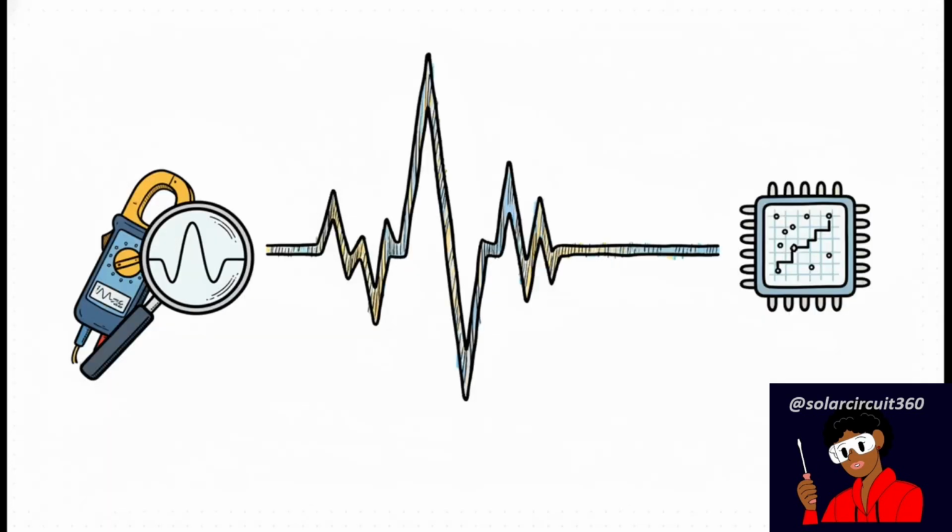This brilliantly illustrates the core conflict. Out in the real world, you've got your handheld clamp meter measuring true RMS current safely on the outside. But inside, you've got the internal logic of the inverter's firmware relying on a completely different internal sampling method. That is exactly why your trusty clamp meter might show a perfectly stable load drawing from the grid, while your inverter is simultaneously screaming at you that you're exporting power. It's two completely different measurement systems interpreting the exact same distorted waveform in two totally different ways.